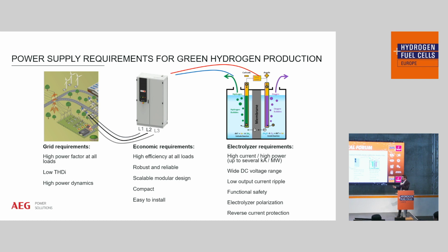On the left-hand side you have the grid requirements. Here, the most important figures of merit are the power factor, which has to be high, as close as possible to 1 normally, and you also have to have a low total harmonic distortion, THDI. Also increasingly important is the provision of power dynamics, to provide the grid demand flexibility to cope with the higher and higher penetration of intermittent renewable energies.